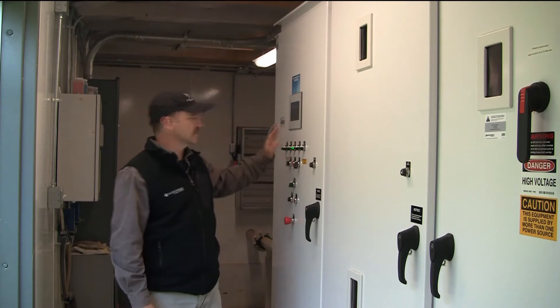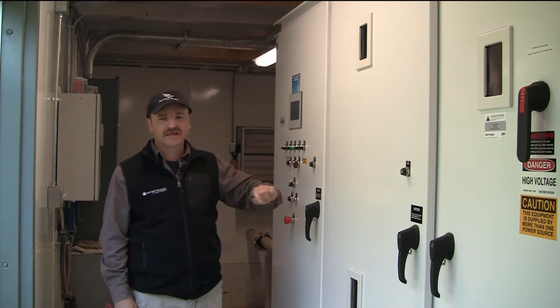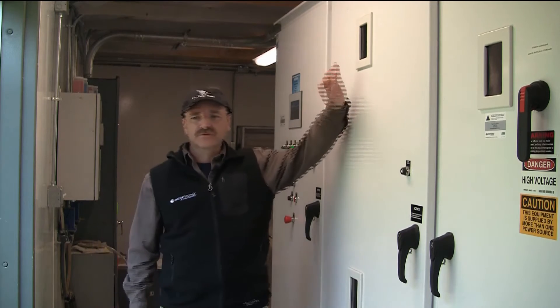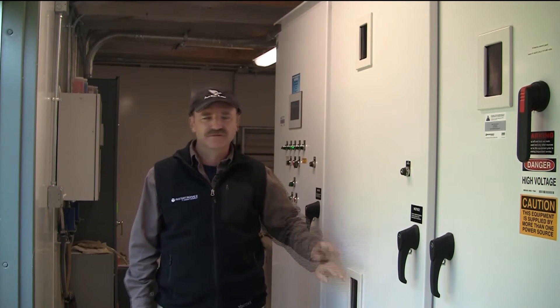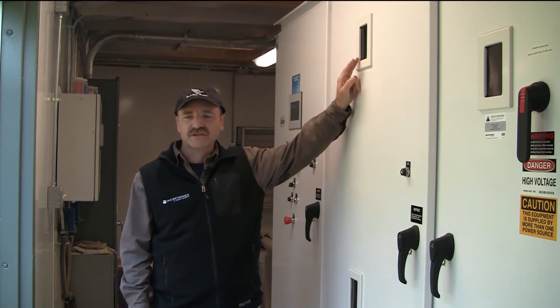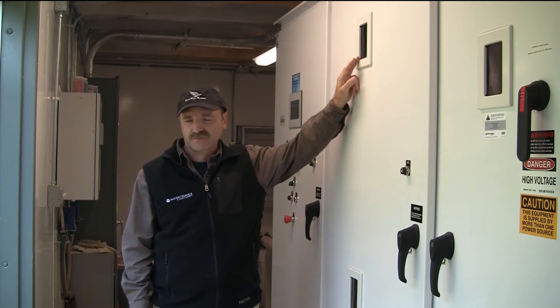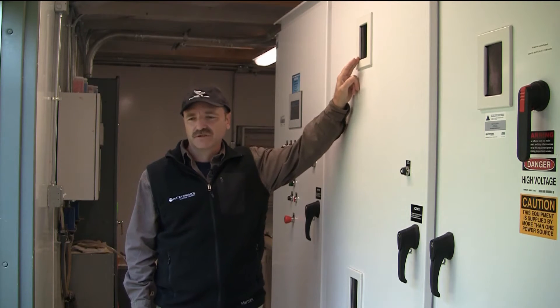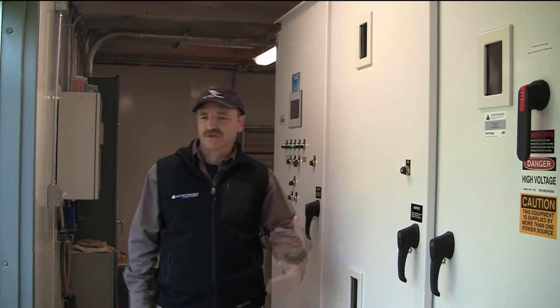So if you've looked at your alarm panel and you've got an issue, the next place I would always look is through your windows. In this particular system there are actually three drives, but you'll be able to see that the drive is either red or showing you an alarm on its display, and that gives me a good idea of what's going on when we talk on the phone.